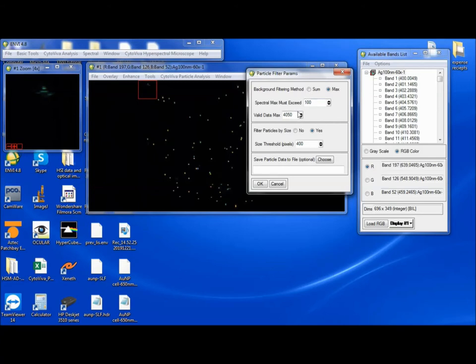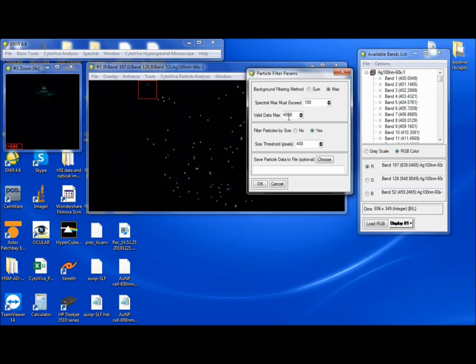And then there's also a data max. So there's a minimum and a maximum, and this maximum is just to ensure that you don't count particles that have clipped. Maybe some particles are extremely bright. Sometimes clipping occurs. It's not the end of the world. However, you probably don't want those particles in your report or you're not interested in the spectrum because the data is clipped.